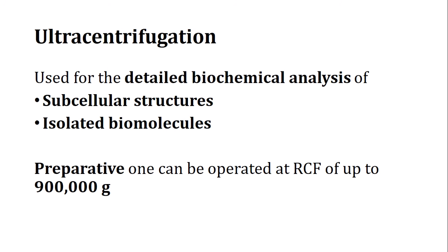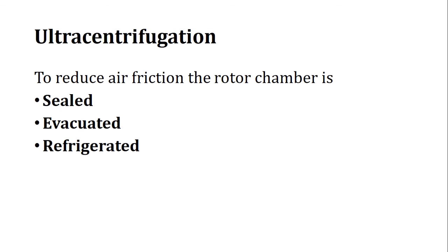The final type is the ultracentrifuge, used for detailed biochemical analysis of subcellular structures and isolated biomolecules. The preparative ultracentrifuge can be operated up to 900,000 RCF (nine lakh g). To reduce air friction, the rotor chamber is sealed, evacuated, and refrigerated. Sealing is required for proper evacuation and also aids in refrigeration.